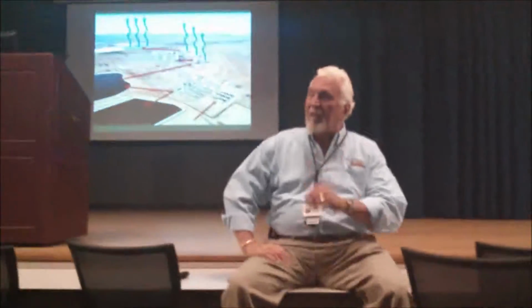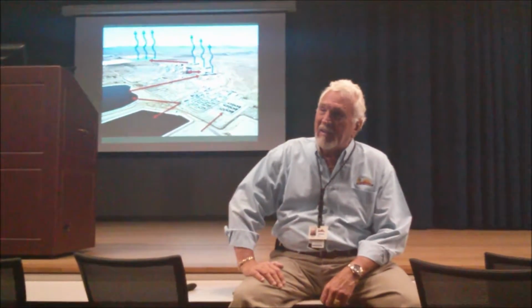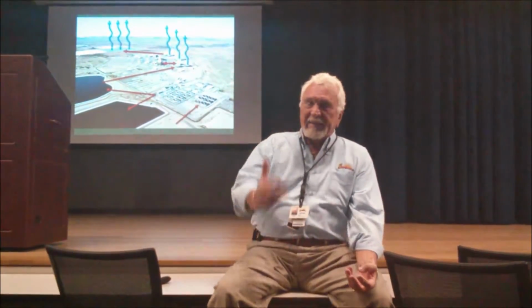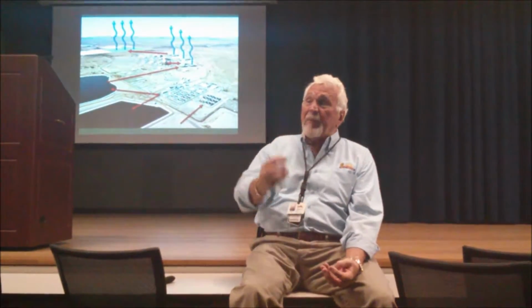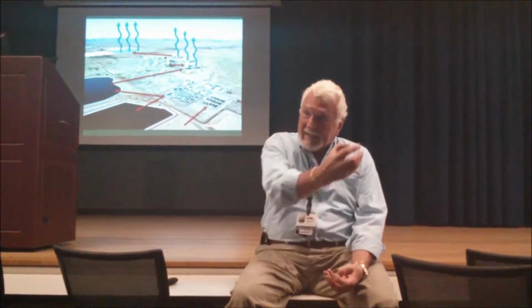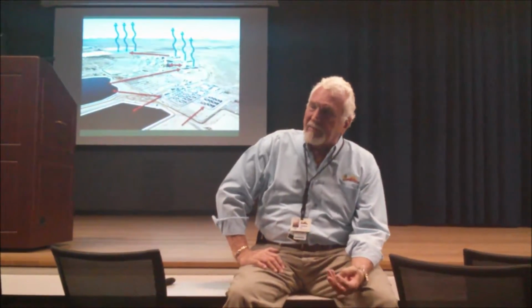You just can't use that leftover energy. I know you couldn't use it for generating electricity, but isn't there some other use for something that needs to be heated? No, and in fact, what we do is maintain a vacuum in our condensers so that the steam remains steam below normal ambient temperatures. We do that to get every little bit of energy out of it.